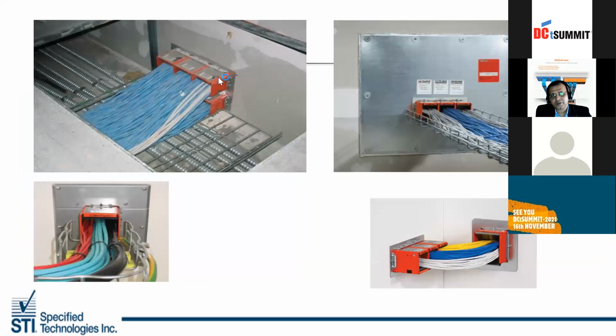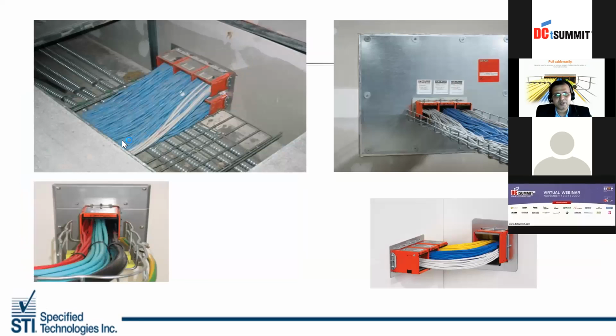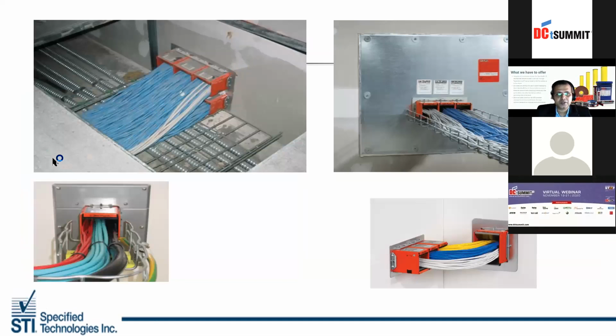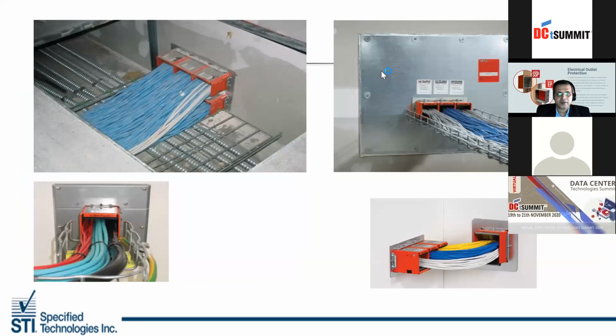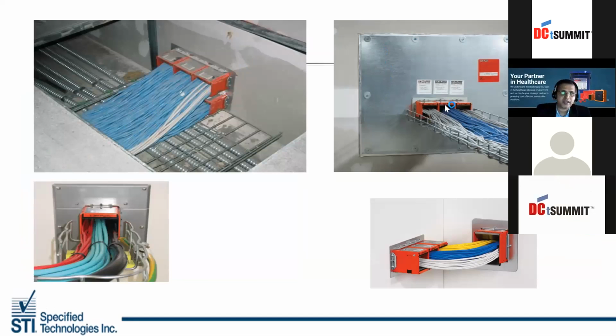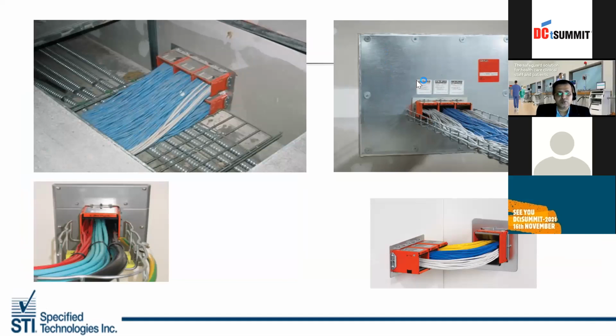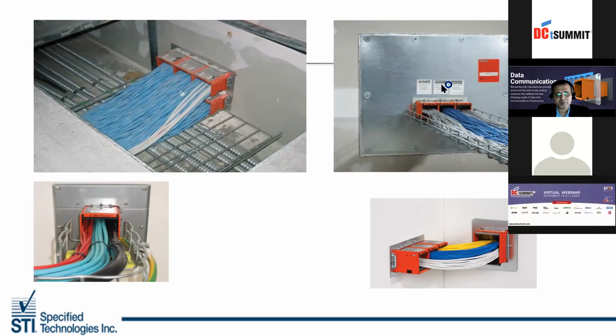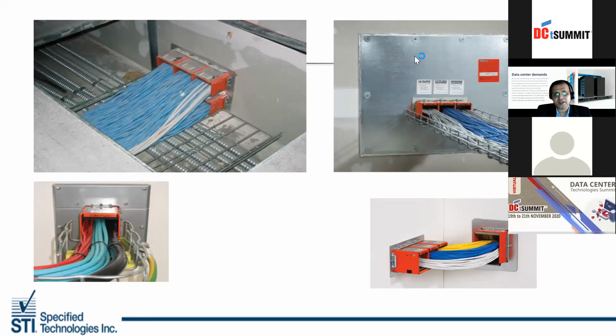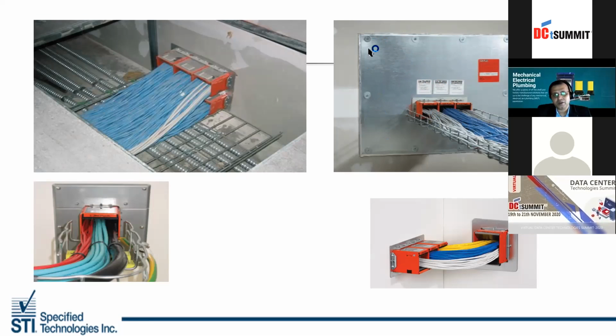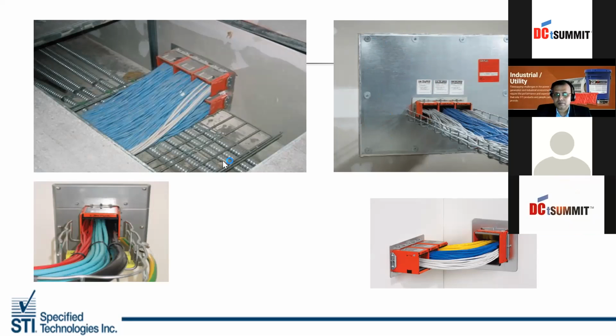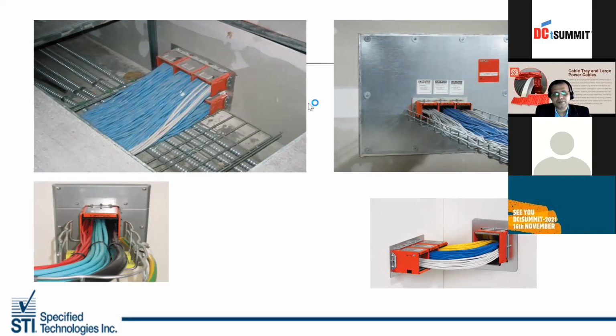Data center scenarios. Earlier, we used to have cables passing below the raised flooring. So this is the scenario where cables are passing below the raised flooring. Here you can see a combination of composite sheet and a cable tray. So in case after, say, 1 or 2 years, you want to add one more cable tray, this part can be easily cut with a machine, and the same cable tray and EZ path can be passed through this without removing all the scenarios. So this combination also acts as a re-enterable solution.